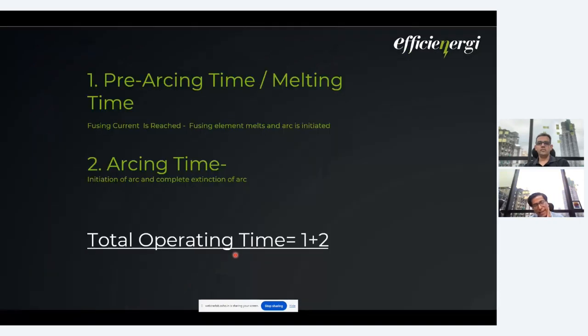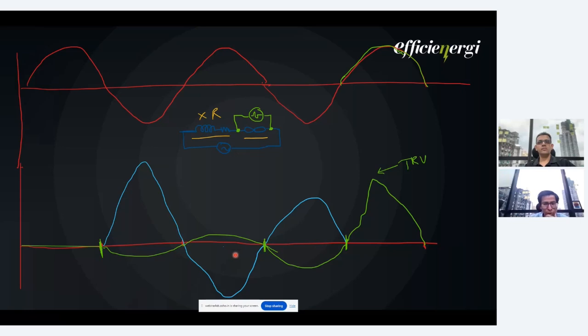Okay, now the IEC standards want every fuse manufacturer to be in line with their standard specified conditions. For that, every manufacturer needs to give the proper TCC for a particular series of fuses. For that, a particular test has to be carried out, and this diagram shows the test that has been carried out. There is one circuit made for injecting a short circuit current. This also has a particular X by R, because you are familiar with the short circuit rating. That is completely based on what short circuit power factor we consider for the short circuit test, and that has to be specified. So this particular test bench is arranged. Then there is a fuse element for which we want to create the TCC.